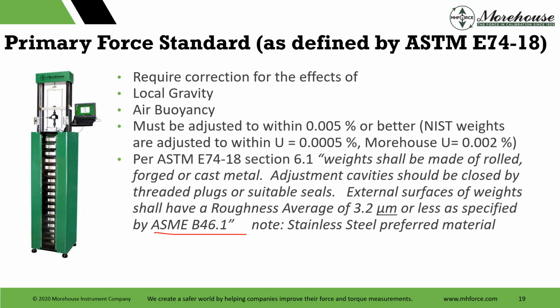So if we use stainless steel, NPL, in the back of E74, there's a study where they did a 10-year study, and they found that if you're using non-magnetized weights, preferably stainless steel, the drift on a deadweight machine is typically less than 0.2 parts per million. That is 0.2 parts per million. Very, very low. Very, very low. That's just looking at these numbers up here. So we got 0.2 parts per million.